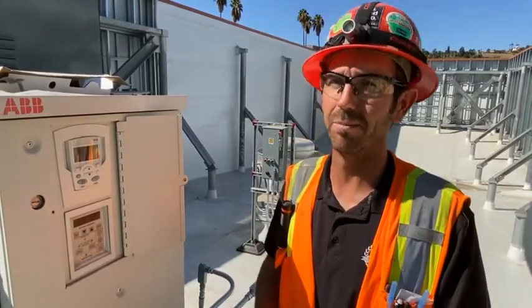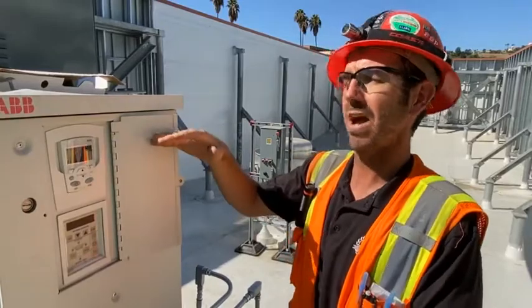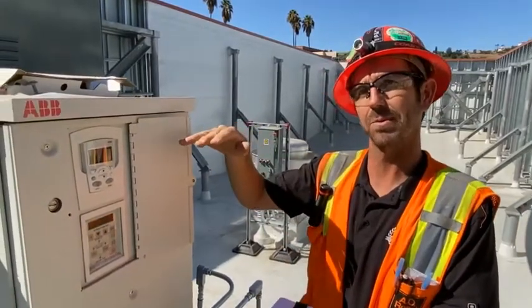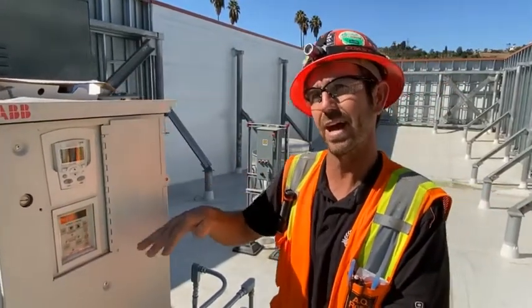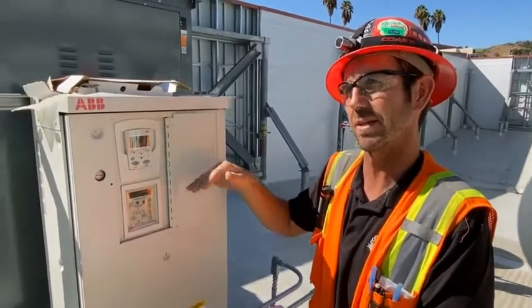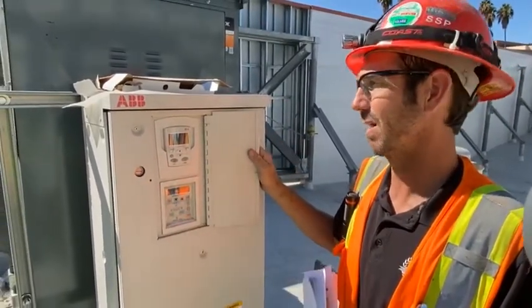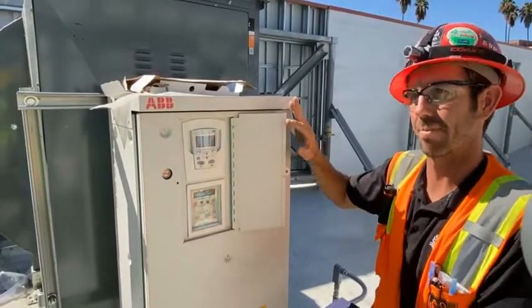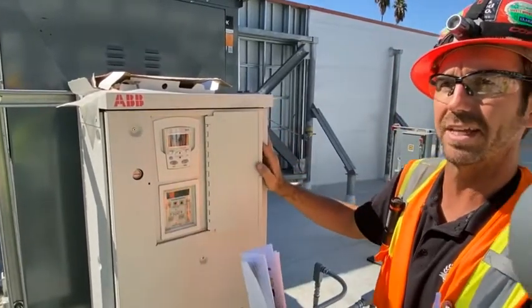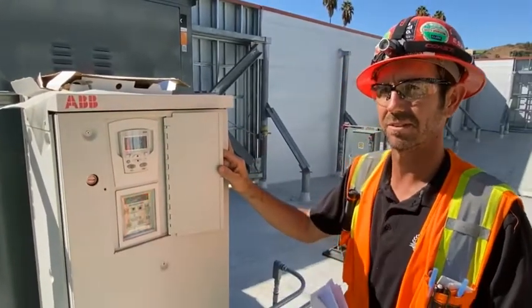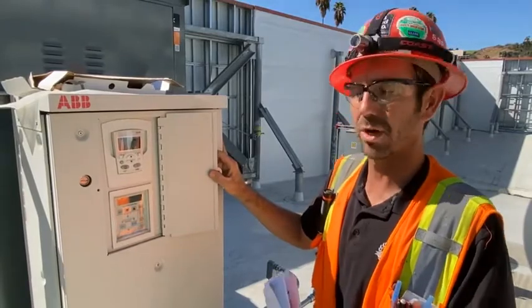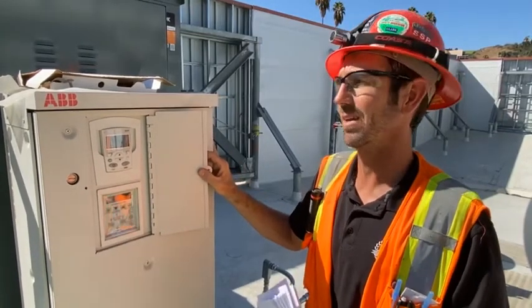Right. Okay. It's just that we have the drive here, so during the balancing procedure we have the option to slow it down and lock in a speed to adjust the airflow that way. That's how this one is operated. It's the only VFD on an exhaust fan in this building. Okay. Just wanted to make sure that makes sense to everyone.